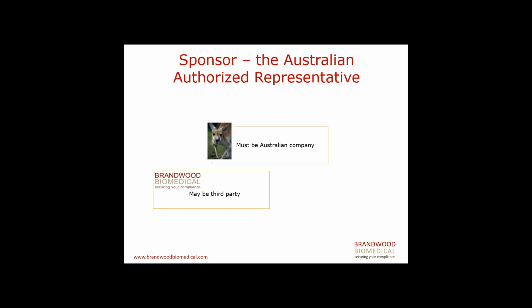However, if the manufacturer assigns the sponsor responsibility to the distributor as well, then if there's any need to change the commercial arrangements, they will require the cooperation of the distributor. And in some cases we've seen manufacturers have to go through the whole device application process and re-register their device under another distributor. And that's where it can get a bit messy. So there are advantages to having a third party.